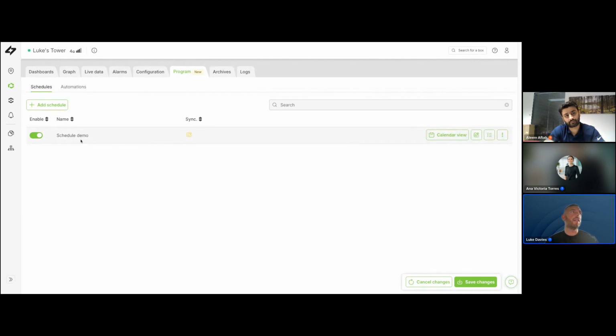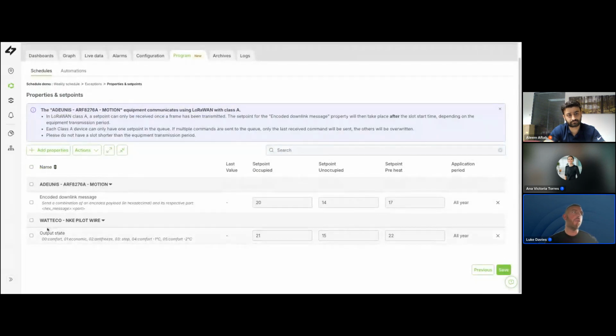If you want to add your automation to a schedule, it's as simple as clicking this button here, and then the equipment that you want it to, you can see the output states here. So the values that you actually send to the box, 0 for comfort, 3 for stop. So you set your values. So the set points itself, during the occupied hours, so during that scheduled 9 to 5, we want it sat at 21 degrees in that school. During unoccupied hours, we're just going to drop that down to 15 degrees.